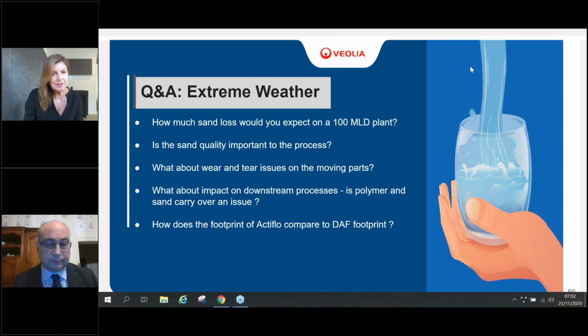There are some other questions here - how much sand loss would you expect on a 100 megaliter a day plant? Well, the sand loss is typically around 1 gram per cubic meter per day, so a 100 megaliter per day plant will lose approximately 100 kilos of sand per day.